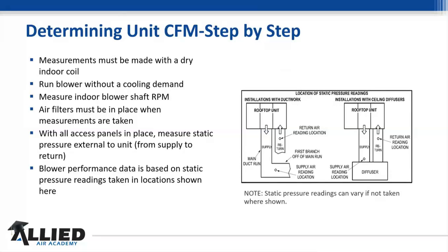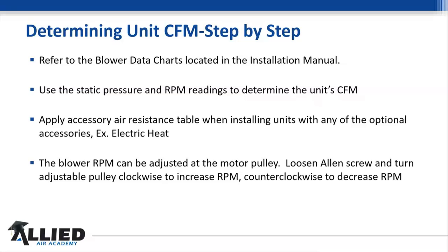Now, when we look right here, this is the ideal place to find your total duct static pressure. And granted, I understand that in some applications, it's going to be tough to get to. You may have to have a lift to get up there. There's some other ways around that, but to get a very accurate reading, if you're really on a job and it's giving you a fit and you have to really be down to brass tacks, we probably need to find a way to do this. Now, I'll show you some alternate methods. I live in the real world too, and I understand that you can't always get to these things, but that's probably one of the better ways to do it.